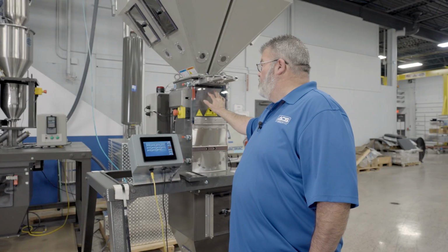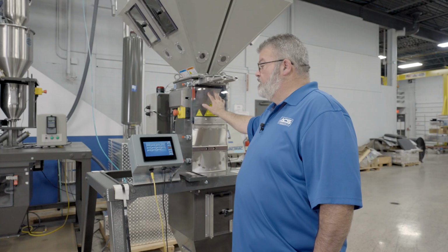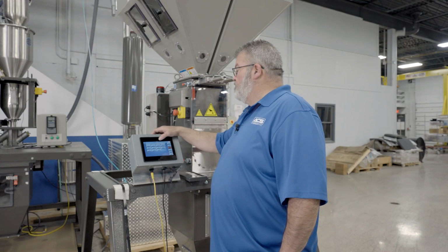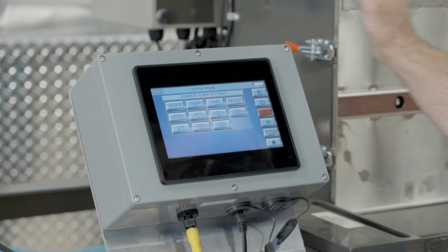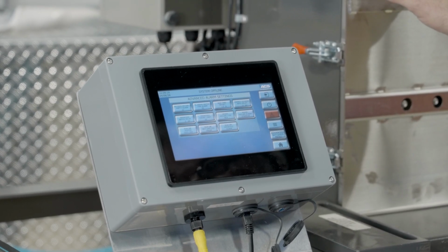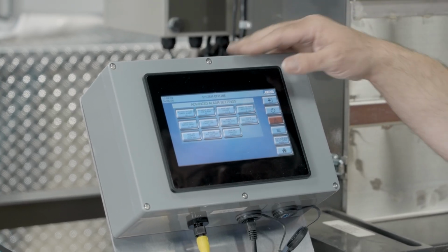So if for some reason the weigh hopper goes 45% above the batch size or whatever you set it to, it's going to give you an over max alarm. Max tare offset. As long as when we empty the weigh hopper, it's within a pound of being 0, we re-zero the weigh hopper before making the next batch.